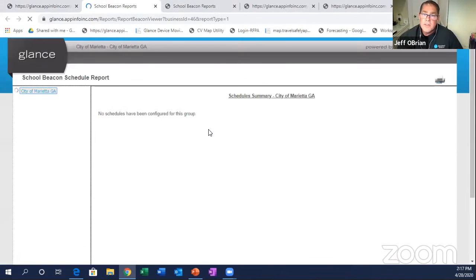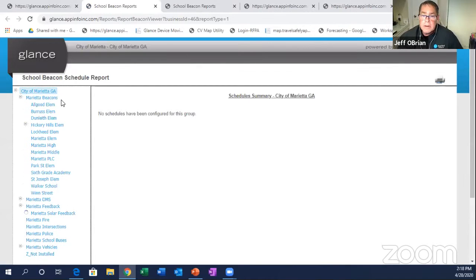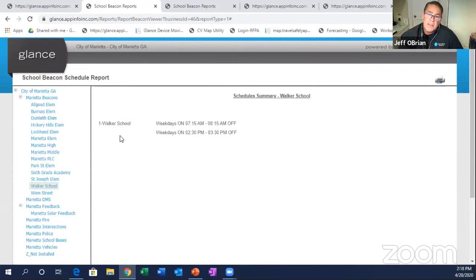Some other things that we can do to confirm is the school beacon schedule report. The Walker School is the one that we just had up. This is the school schedule that's in each of the devices assigned to this particular business. Just as a confirmation, we looked and saw that those units came on right at 7:15 and off right at 8:15 and so on for the afternoon.